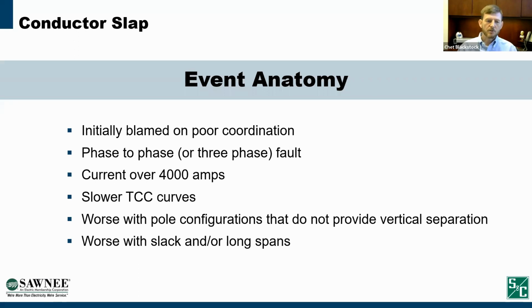Conductor slap always requires at least 2 phases to be involved. So it's phase to phase or 3-phase faults. We found, and we found some research that supported this, that it's more frequent for current over 4,000 amps, which is not uncommon at all on our system. We frequently have fault currents of that magnitude on our system.